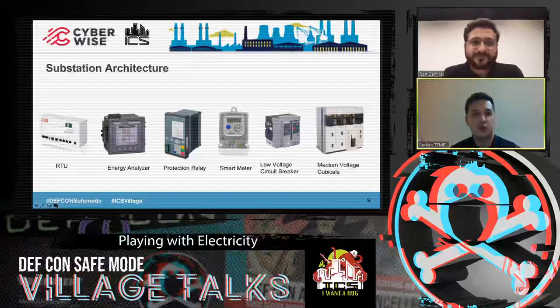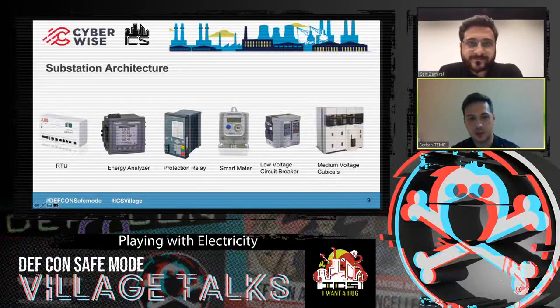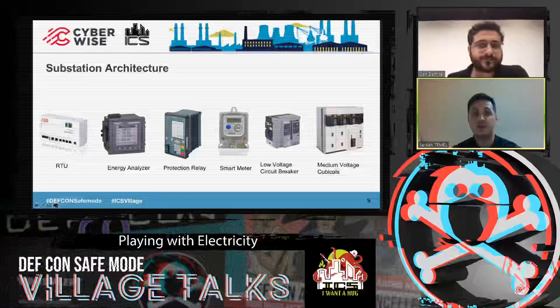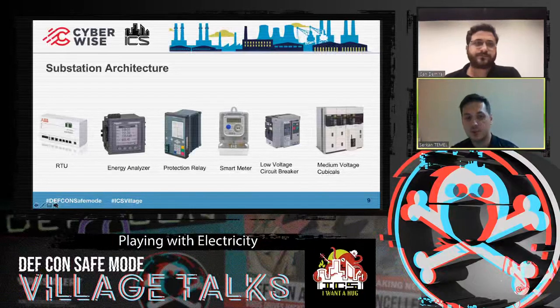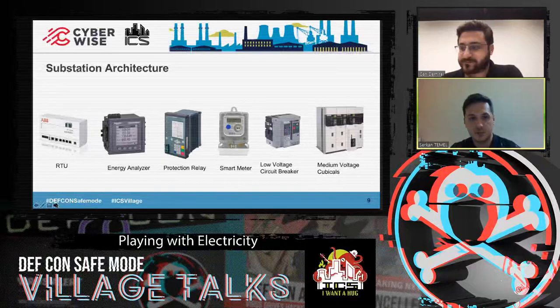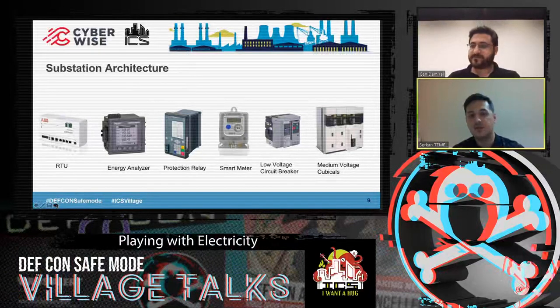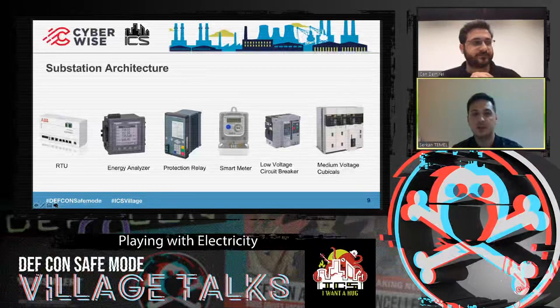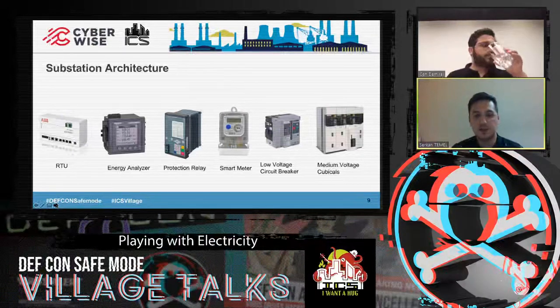Now we have talked about the substation architecture. In the substation architecture and distribution substation process, we have some main devices for the process we use. The first one is RTU. RTU is a telecontroller which connects field devices to the SCADA systems. We think of RTU as a data concentrator or data transfer device.